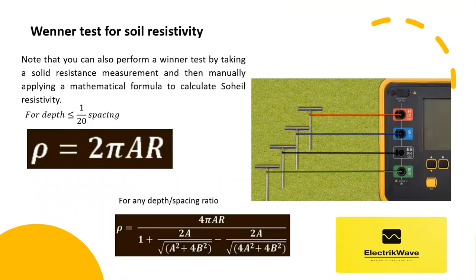Note that you can also perform a Wenner test by taking a soil resistance measurement and then manually applying a mathematical formula to calculate soil resistivity as shown here, for depth less than or equal to 1/20th spacing, and for any depth by spacing ratio.